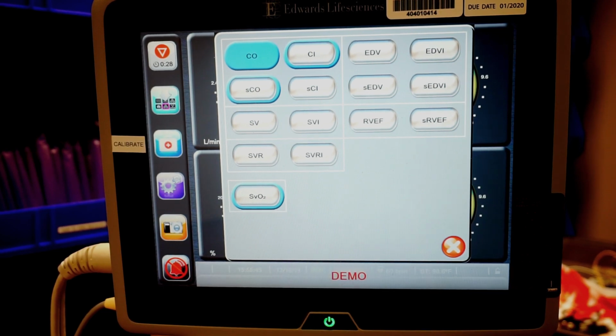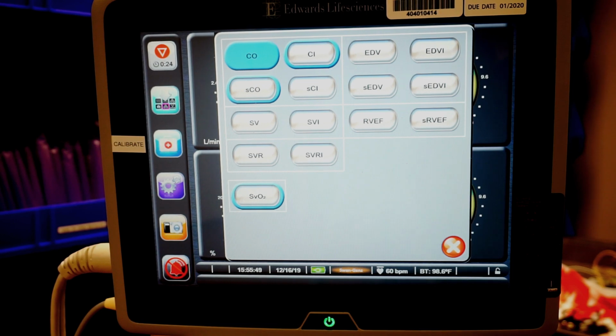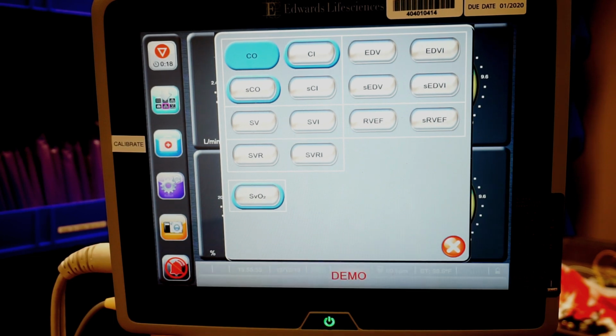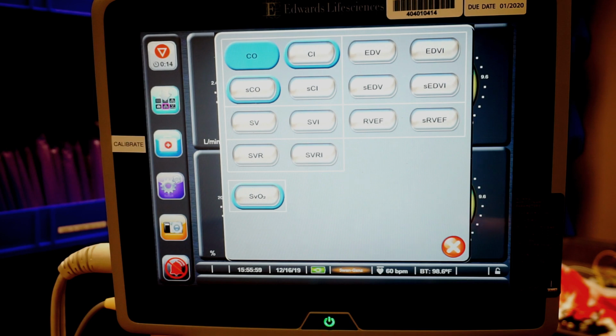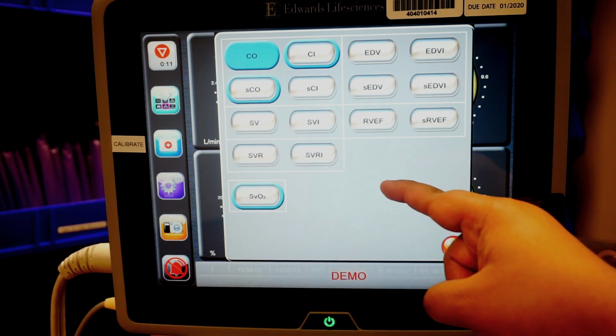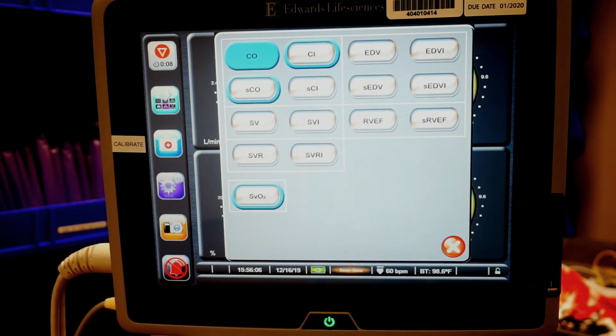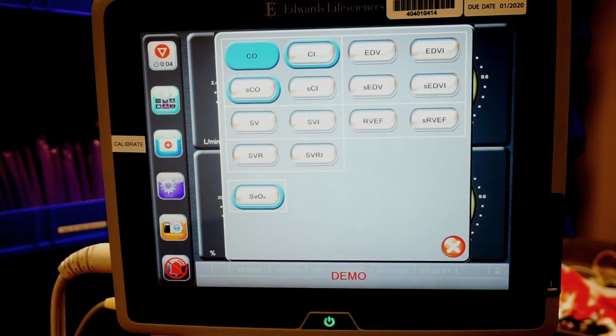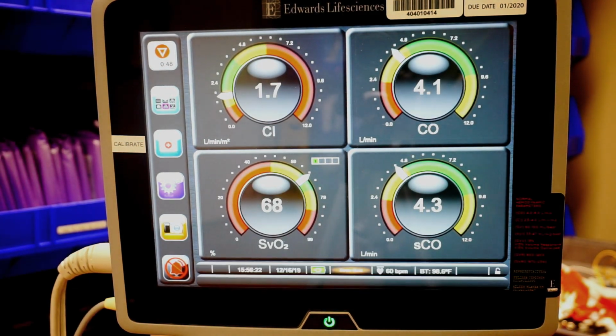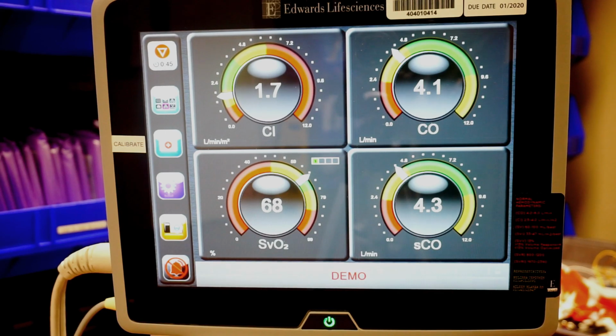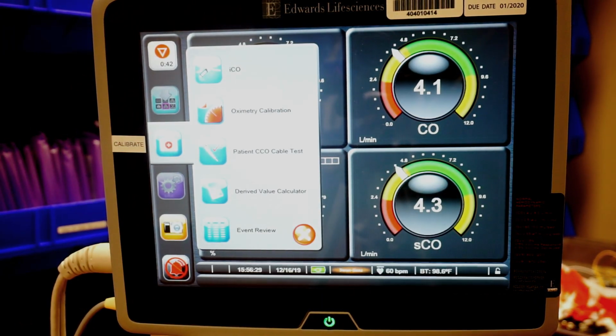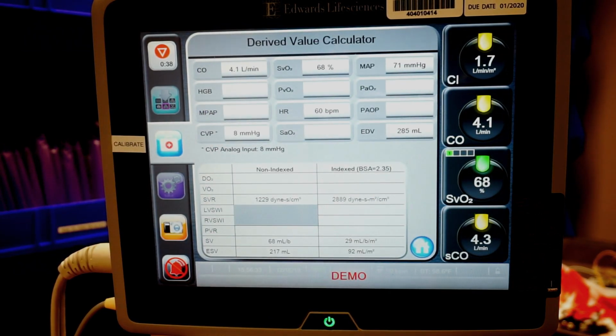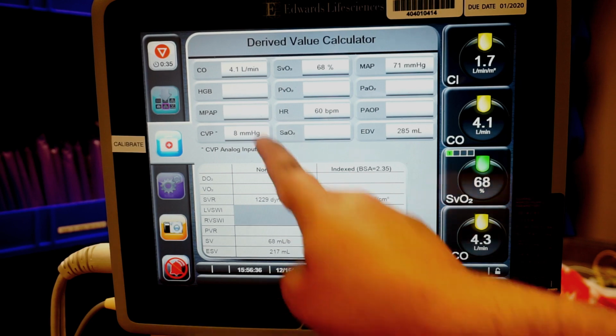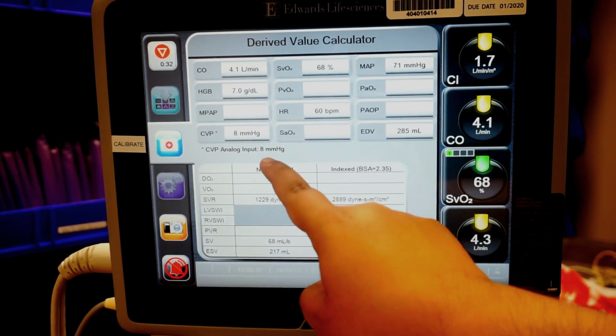This monitor does not get values from our cardiac monitors such as heart rate, arterial blood pressure, MAP, or our PA pressures. It's not getting that information, so it can't calculate your SVR. So these top 4 and your SvO2 are really the limitations of our monitor currently. Now if I want to get calculations on certain hemodynamic values, I can go to my nurse's bag and open the derived value calculator. Essentially here I can put in all this information.